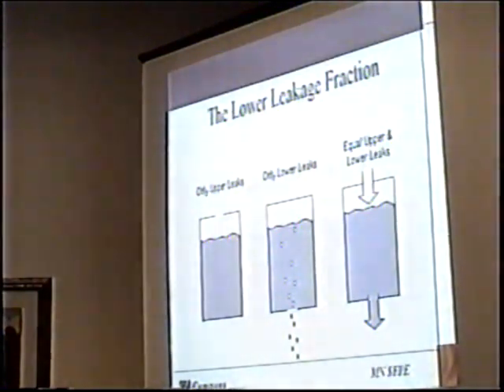Most people don't like to do them to determine exactly what this split is. The reason I'm spending so much time on this, though, is that I've been told by a couple of professionals in the field that a lot of door fan operators like to guesstimate what this value is. A dangerous practice, as you'll see. Nonetheless, we already know that it's the most sensitive input parameter that we have. So let's move forward here, knowing that that's our worst case assumption.